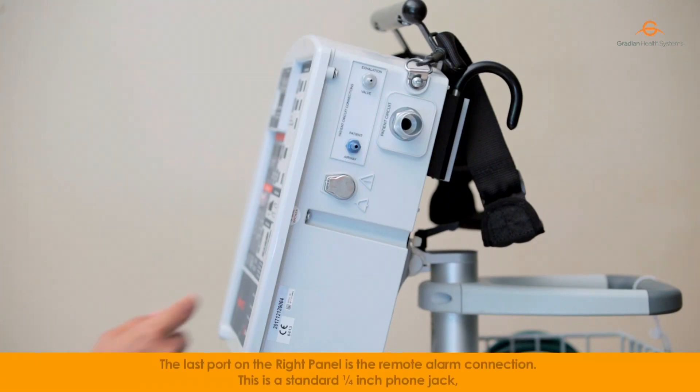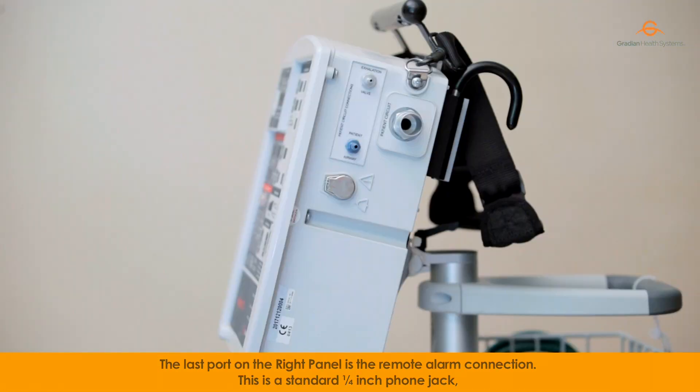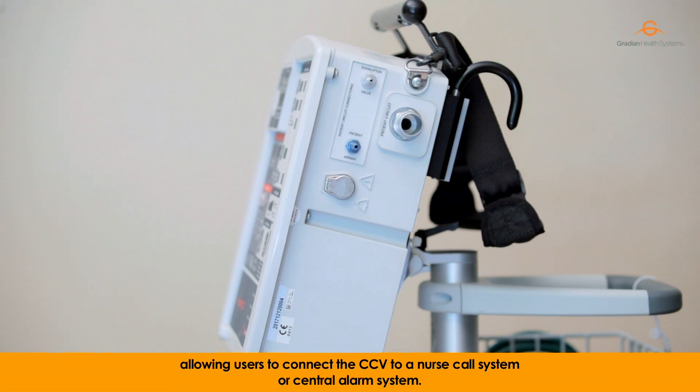The last port on the right panel is the remote alarm connection. This is a standard quarter-inch phone jack allowing users to connect the CCV to a nurse call system or a central alarm system.